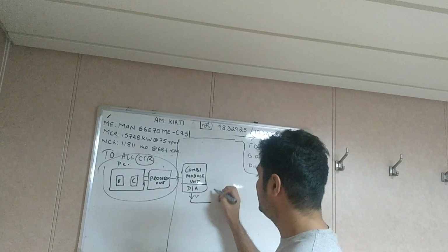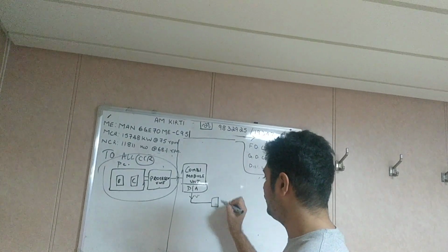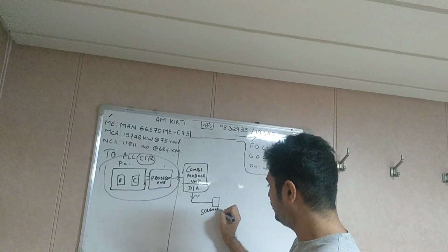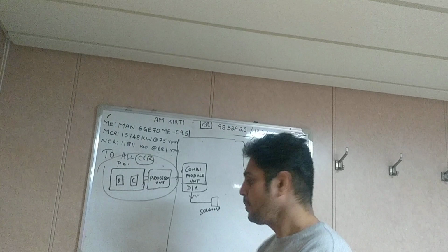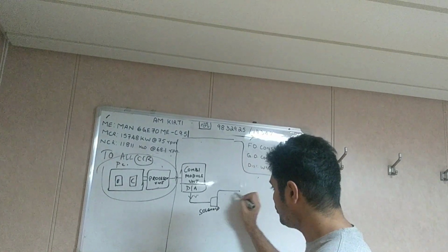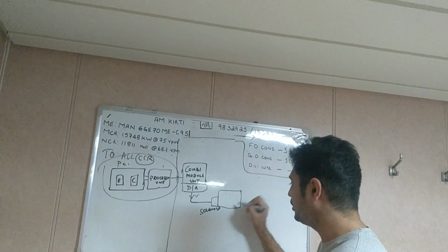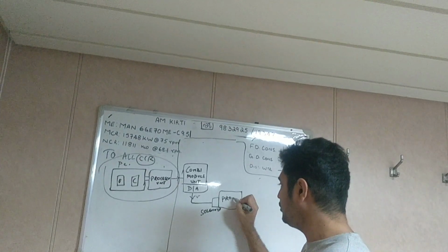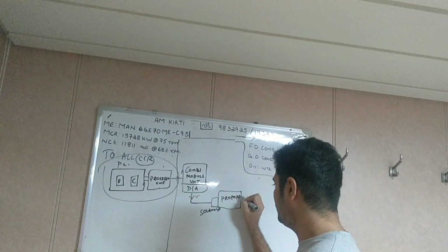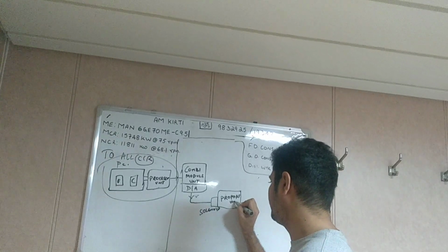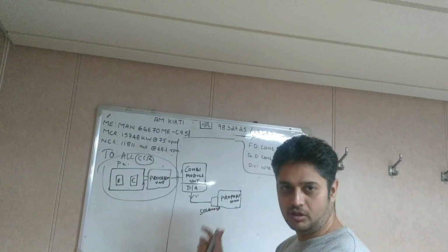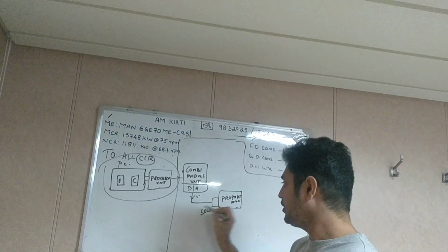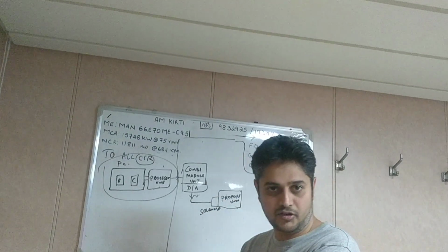Here you have the solenoid, which is operating a proportional valve, mostly a 2/3 proportional, so basically there is a spool here. It is a solenoid operated proportional valve. So when you give the signal, this solenoid becomes energized.